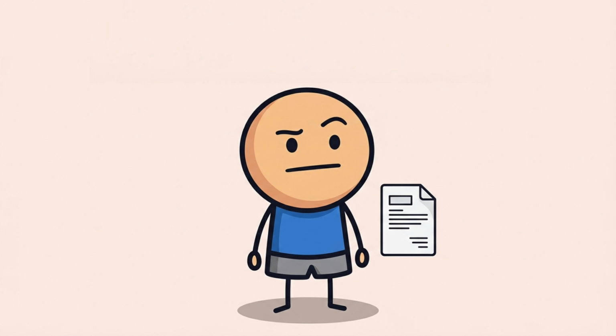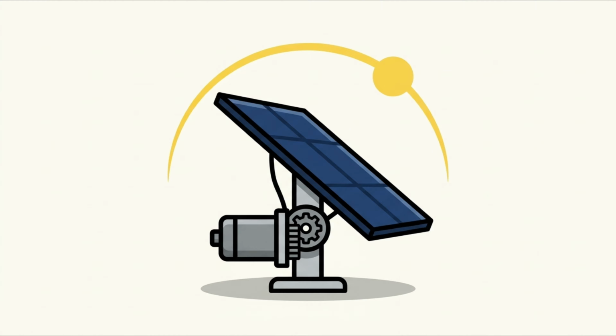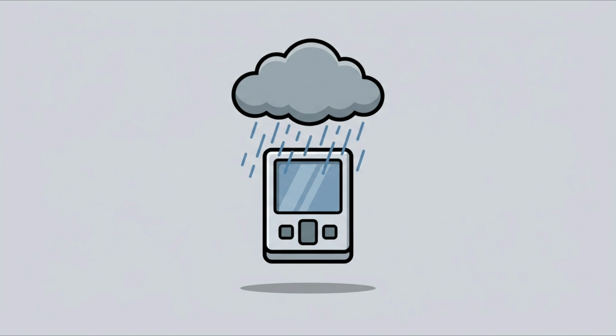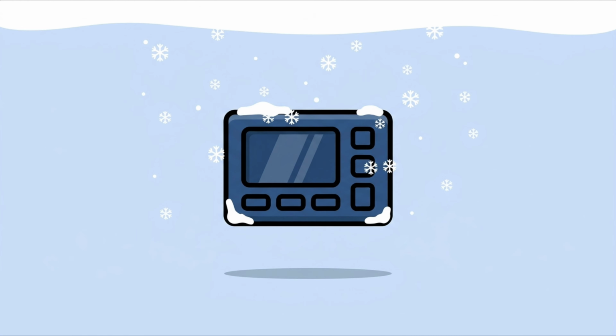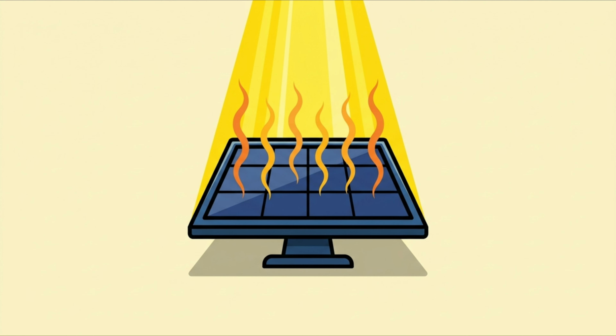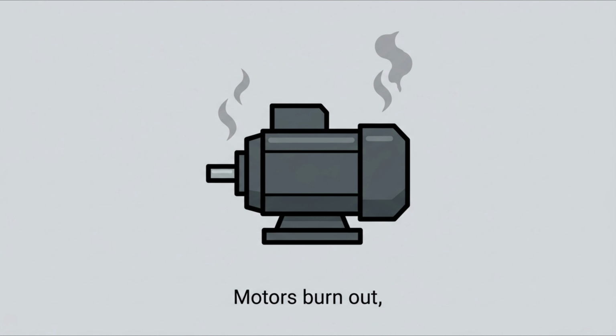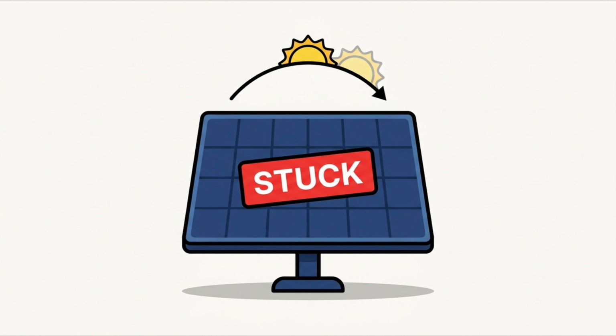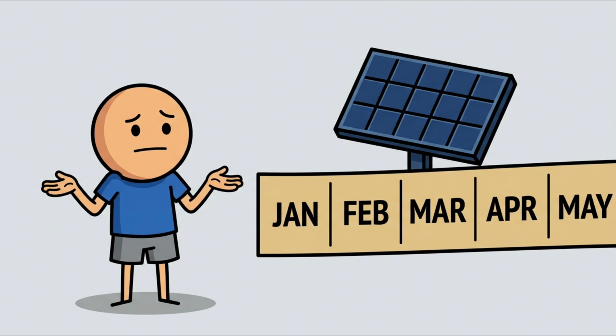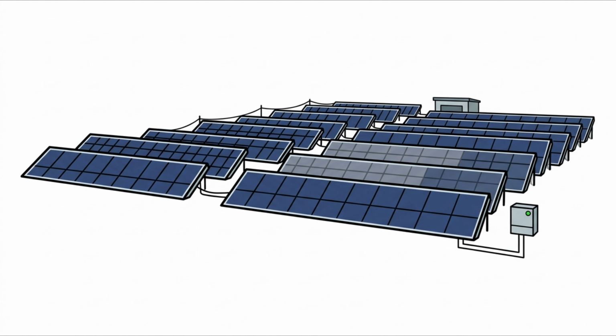Here's a cost most people never think to ask about until the engineering report lands on their desk. Trackers, the motorized systems that tilt panels to follow the sun, are mechanical devices in a field getting rained on, snowed on, and baked by UV exposure for decades. They fail, motors burn out, gearboxes wear down, and a stuck tracker doesn't just stop tracking, it can leave panels angled incorrectly for months if nobody catches it, quietly reducing the farm's output without triggering an obvious alarm.